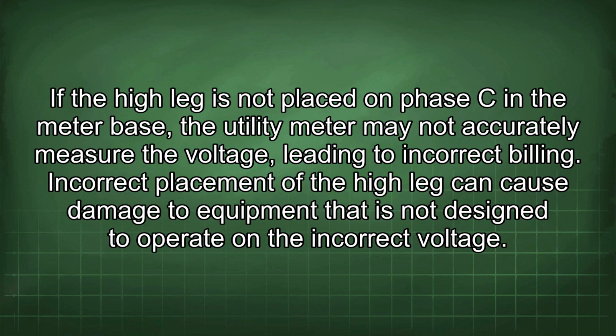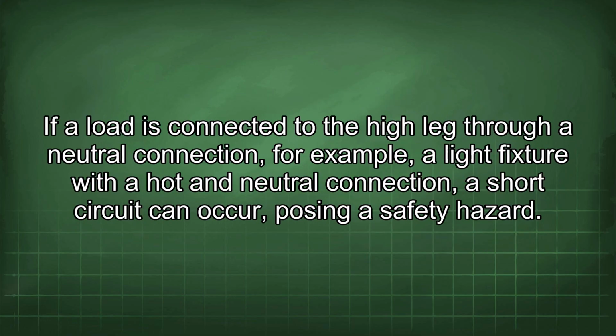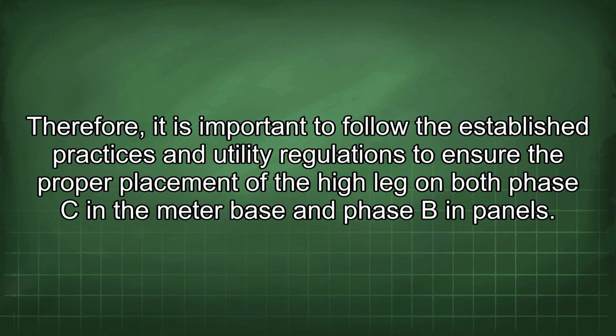Incorrect placement of the high leg can cause damage to equipment that is not designed to operate on the incorrect voltage. If a load is connected to the high leg through a neutral connection, for example, a light fixture with a hot and neutral connection, a short circuit can occur, posing a safety hazard. Therefore, it is important to follow the established practices and utility regulations to ensure the proper placement of the high leg on both phase C in the meter base and phase B in panels.